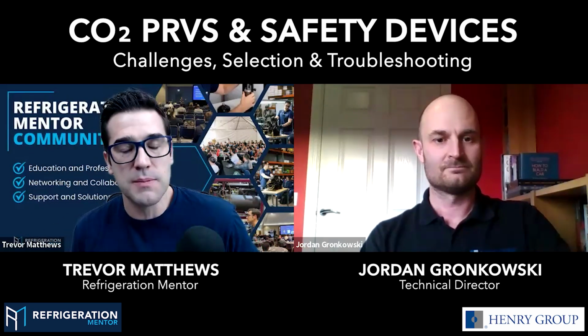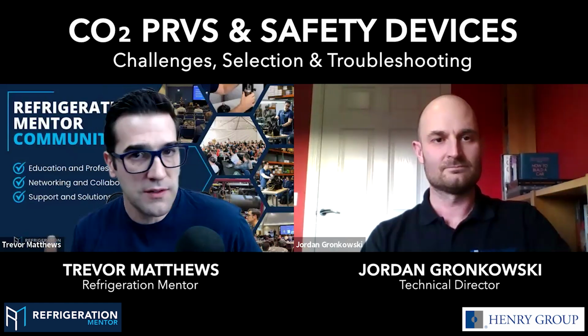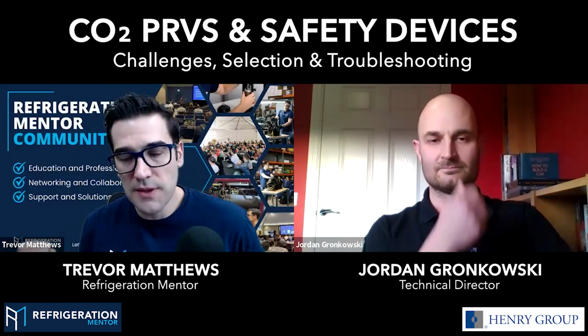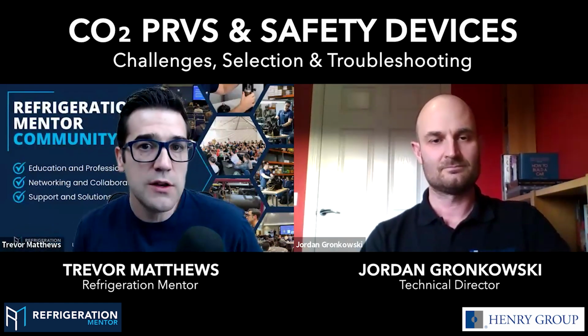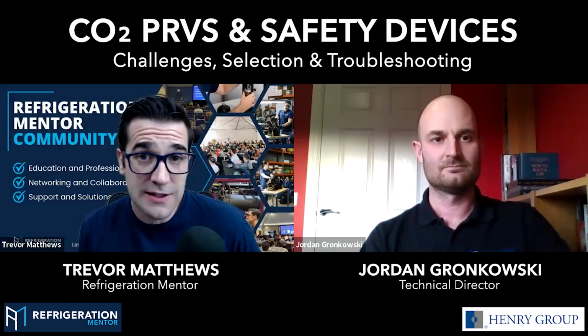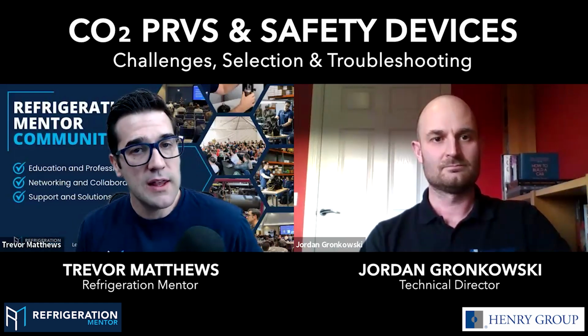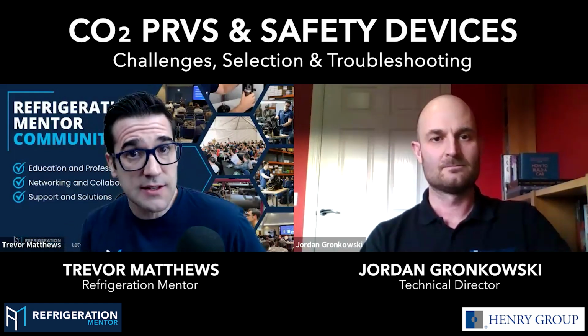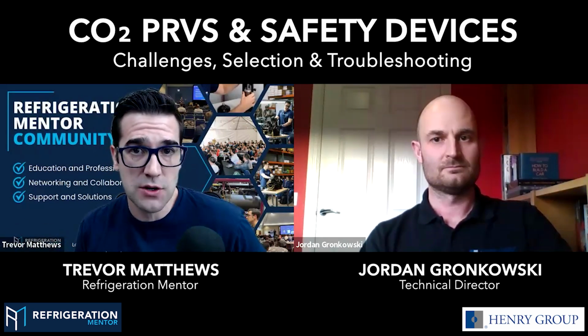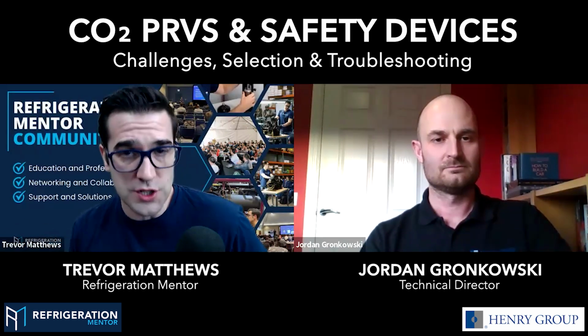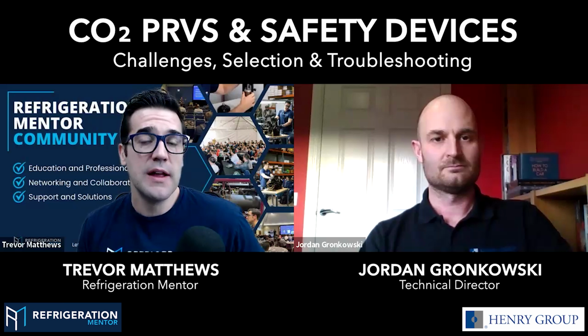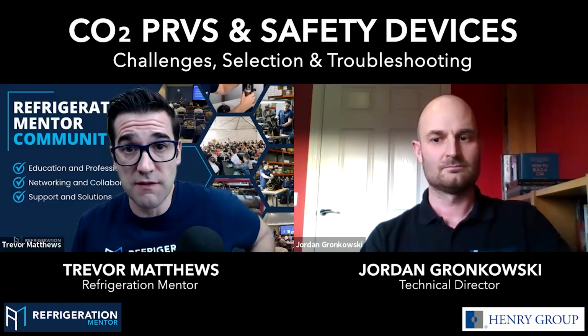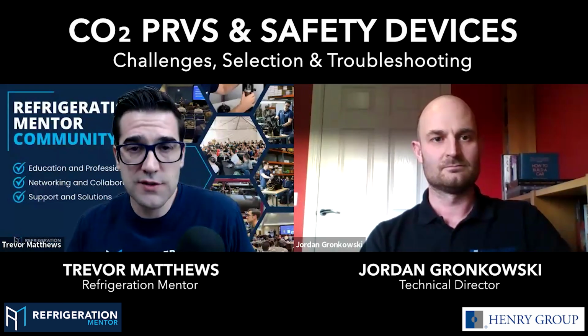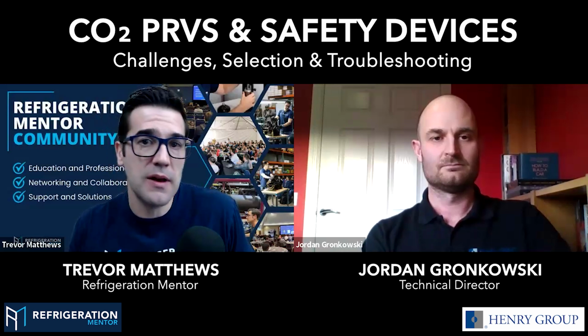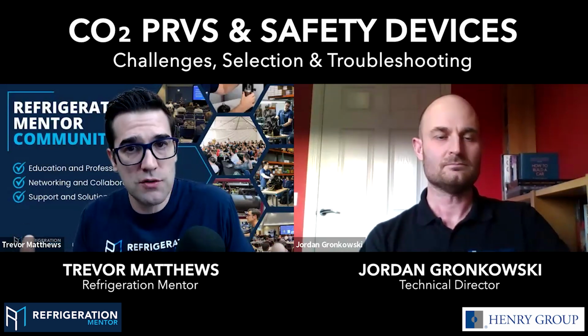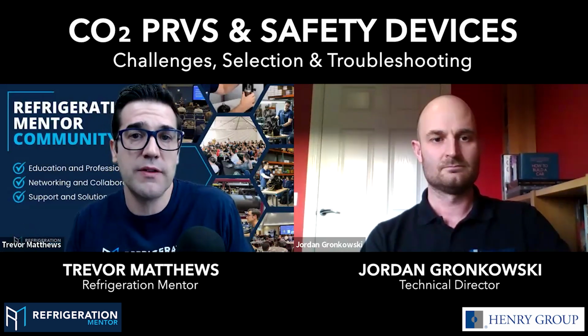We met back at Chilventa, and we stopped in and I had a conversation because honestly, I know what pressure reliefs are. I know what they do, but it's something that we don't understand enough. Well, a lot of people that I talk to in my circles, we know that if you have a catastrophic event, they are there to protect the system so you don't have an explosion or something blowing up, because these are vessels with refrigerant or some sort of chemical inside them, and ours is refrigerant, but you have these pressure reliefs to stop these catastrophic events.